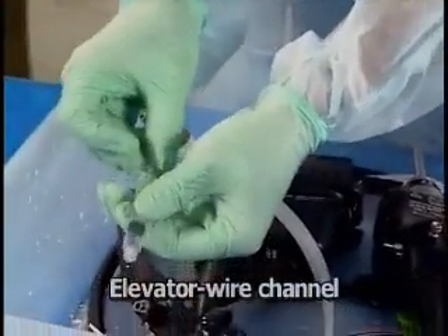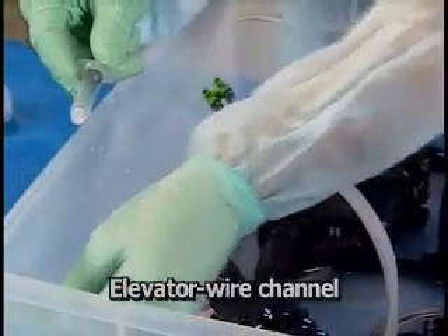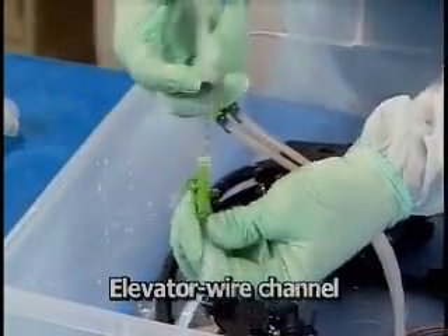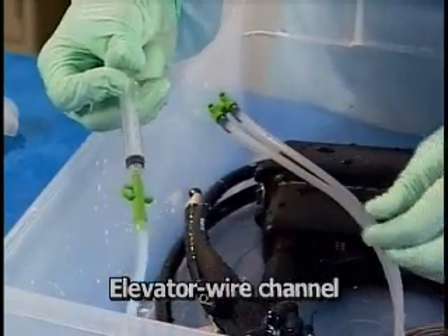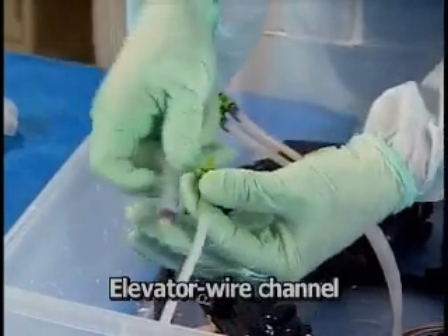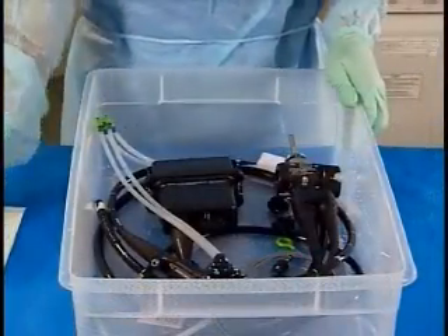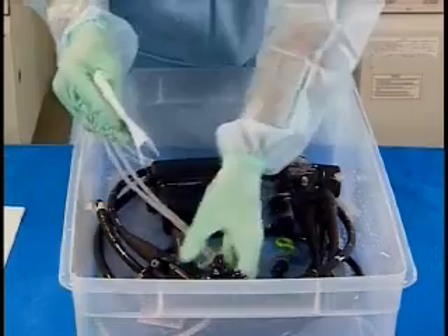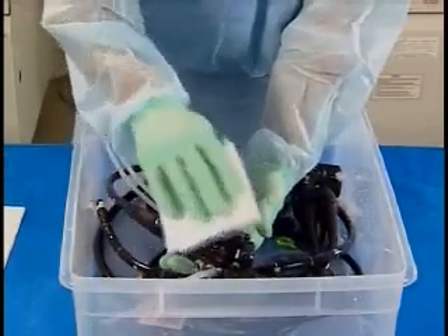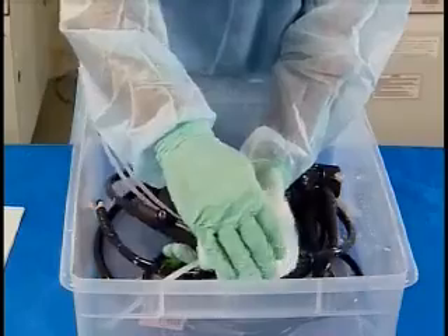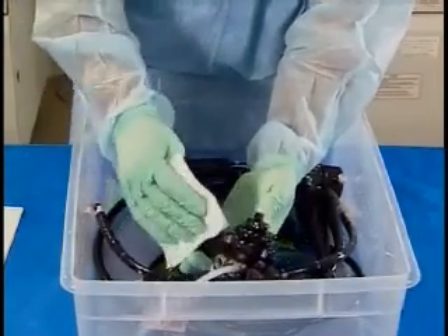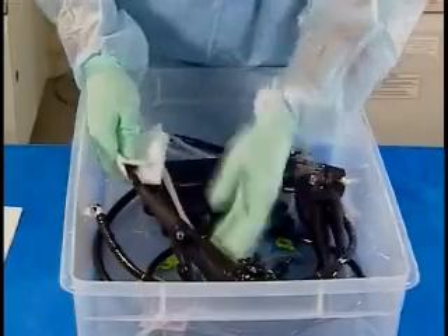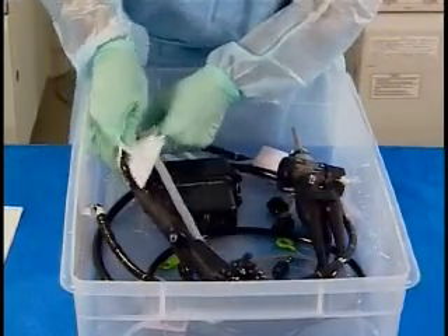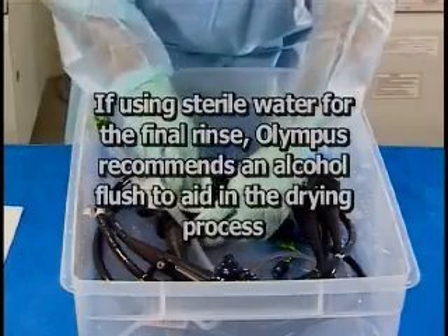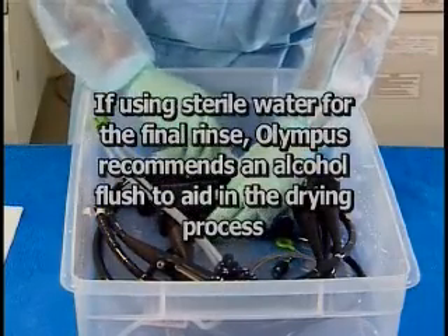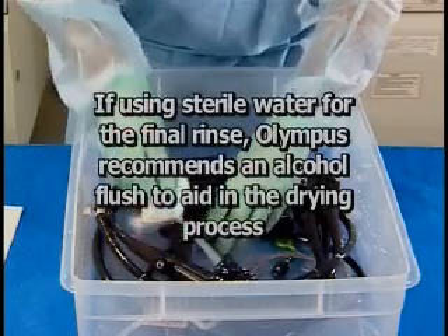If you are reprocessing an endoscope with an elevator, inject air into the elevator wire channel in order to expel rinse water from this channel as well. Use a sterile lint-free cloth to thoroughly dry the external surfaces of the endoscope and reprocessing accessories. In the event that non-sterile water was used for the final rinse, perform an alcohol flush of the endoscope channels. If using sterile water for the rinse, Olympus recommends an alcohol flush to aid in the drying process.